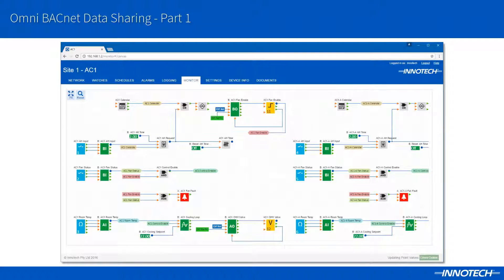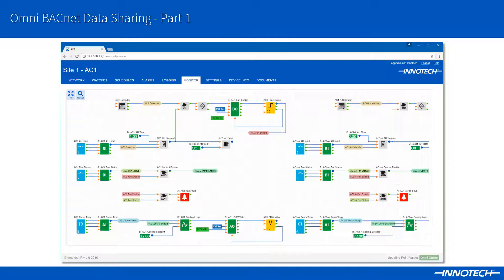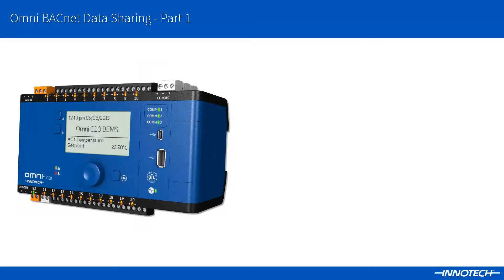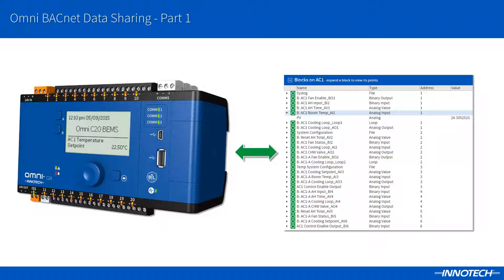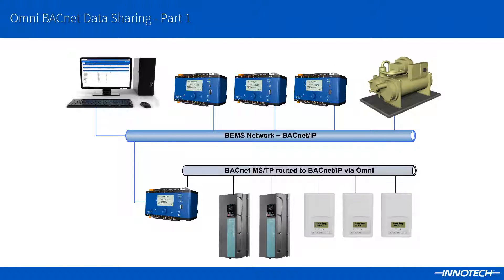When programming the OMNI controller, we can utilise BACnet object blocks — the green block shown — to allow other BACnet devices or clients to view and request block values over the BACnet network. Once configured, OMNI is a BACnet device with objects, providing a fully native BACnet solution. This can open new possibilities for data sharing, as each BACnet block object can be seen from any BACnet device or client, providing global data on the BACnet network.